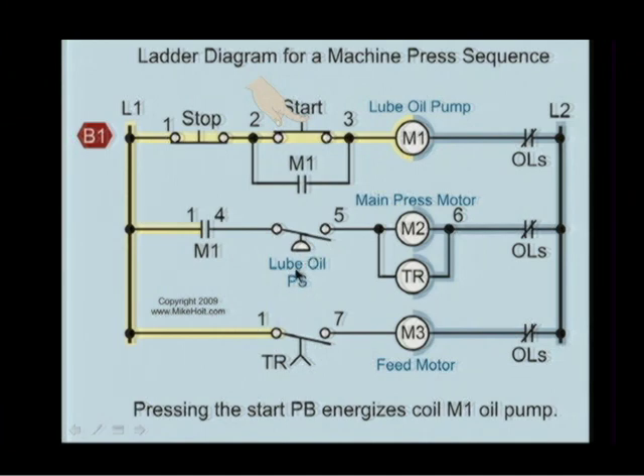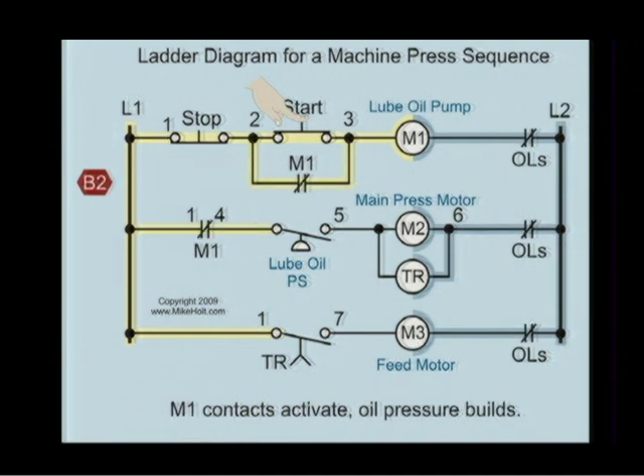Once it gets to the point of sufficient pressure, it closes this contact. That immediately starts the main press. Also, it starts the time delay relay, which now, okay, I got the oil going, I got the main press now running, and then there's some kind of time delay. Dennis, you showed us yesterday, or Steve, you did all the different time delay configurations and however you wanted to do. Then, let's say 5 seconds later, this closes. Now the third motor is energized.